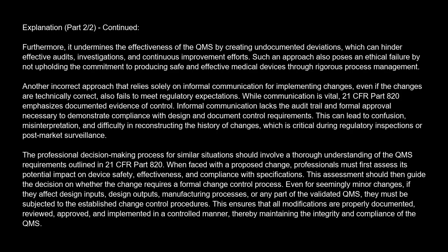When faced with a proposed change, professionals must first assess its potential impact on device safety, effectiveness, and compliance with specifications. This assessment should then guide the decision on whether the change requires a formal change control process. Even for seemingly minor changes, if they affect design inputs, design outputs, manufacturing processes, or any part of the validated QMS, they must be subjected to the established change control procedures. This ensures that all modifications are properly documented, reviewed, approved, and implemented in a controlled manner, thereby maintaining the integrity and compliance of the QMS.